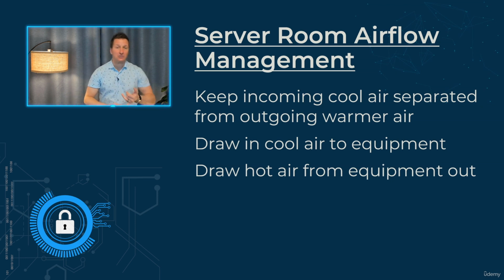So we need to make sure that we keep incoming cool air that's used to cool down equipment in a server room or a data center, that incoming cool air, either from the outside or from an air conditioning unit, it needs to be kept separate from the warm air coming out of equipment that's being exhausted out of the back of equipment. Usually it's the back. So we need to draw in cool air to cool down equipment, and we need a mechanism to draw warm air out. And usually this means we have to think about keeping cold and warm air separate.